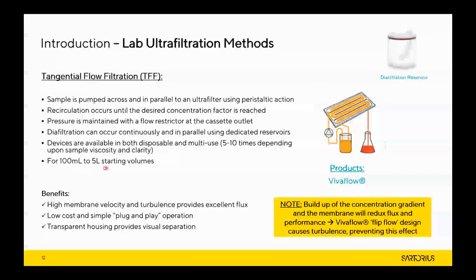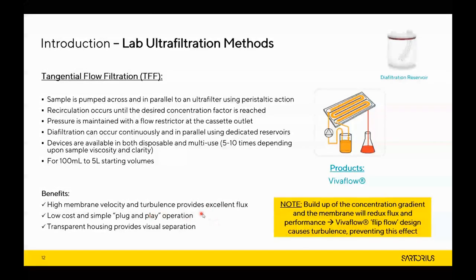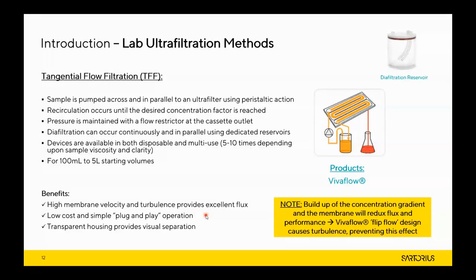The high membrane velocity and turbulence that the flip-flow channels provide give excellent flux — essentially the separation efficiency of the process. TFF devices are relatively low cost with simple plug-and-play operation, and the transparent housing provides visual separation monitoring. A key distinction from process-scale TFF is that lab-based TFF does not require large capital equipment, filter holders, pressure control systems, or complex software and recording systems.